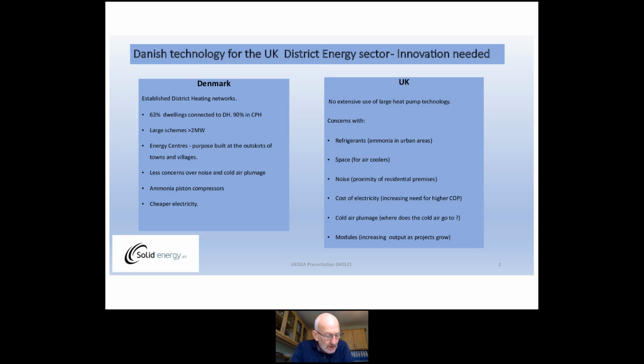On this slide, I've listed the main characteristics and issues relating to the use of heat pumps in Denmark and in the UK. In Denmark, low temperature district heating is very much the normal method for heating buildings, unlike in the UK with a very low percentage of buildings connected. Here in the UK, we have to be careful. Ammonia is not always considered to be the first choice of refrigerants. Energy centres are often located in urban areas where space and noise considerations are a concern.